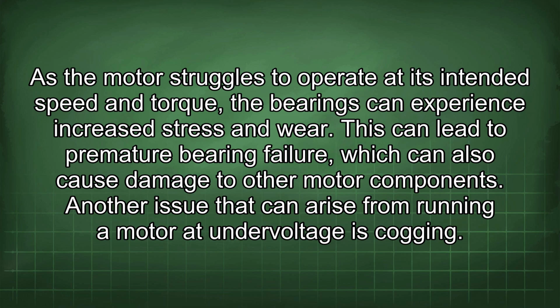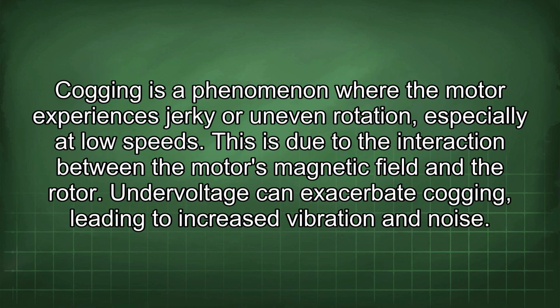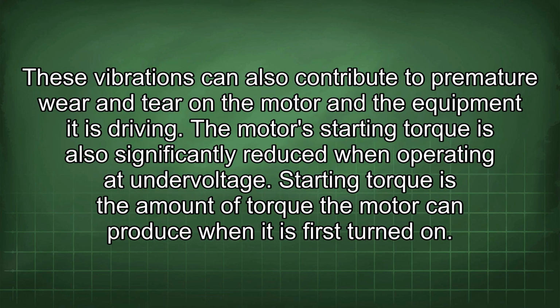Another issue that can arise from running a motor at undervoltage is cogging. Cogging is a phenomenon where the motor experiences jerky or uneven rotation, especially at low speeds. This is due to the interaction between the motor's magnetic field and the rotor. Undervoltage can exacerbate cogging, leading to increased vibration and noise. These vibrations can also contribute to premature wear and tear on the motor and the equipment it is driving.